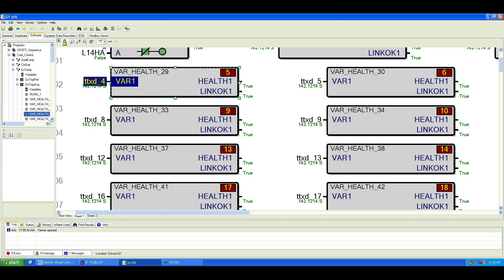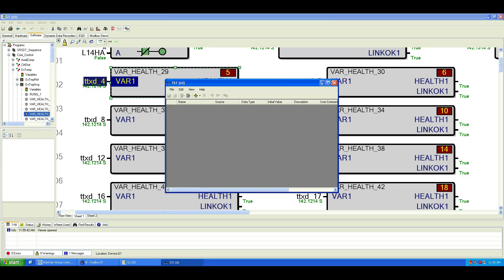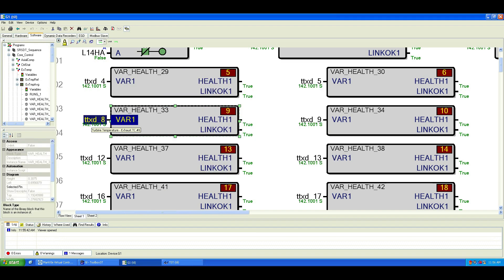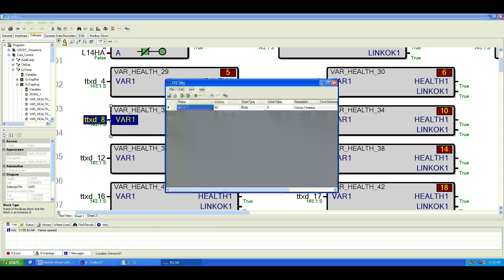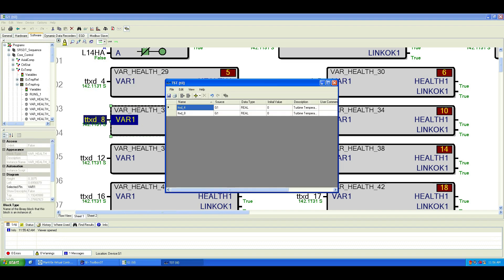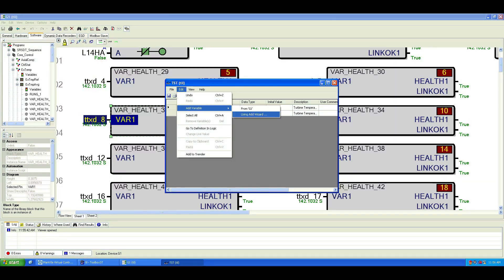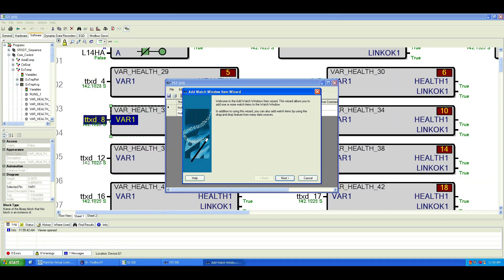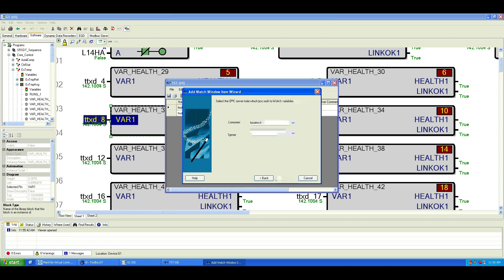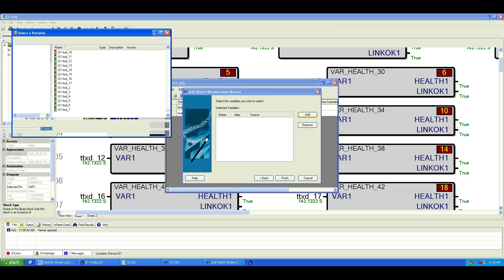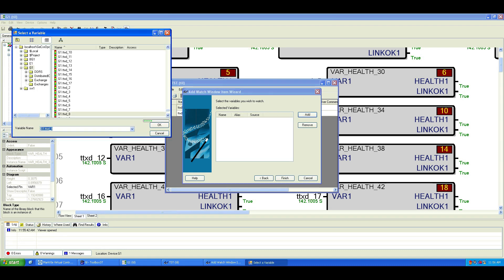Now it's time to add variables. You can either drag and drop variables into the Watch Window, or go to File > Add Variable and use the Add Wizard. Click Next, then choose Add from OPC Server — this is my preferred method. Click Next, then Add, select the variable you want to monitor, click OK, then Finish.